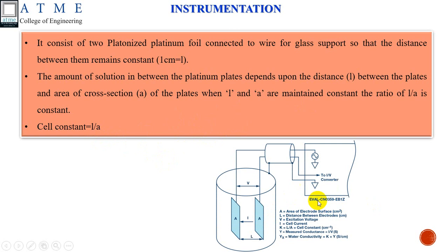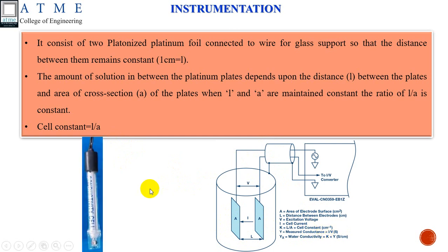This is a typical conductivity setup. A is the area of electrode surface in cm², and L is the length between the two electrodes in centimeters. If they are kept constant, we call it the cell constant, K = L/A. This is a typical conductivity cell.